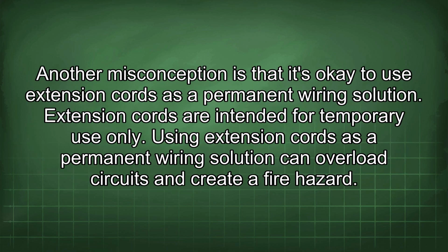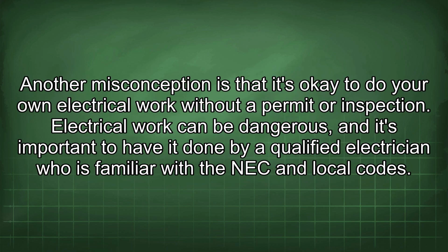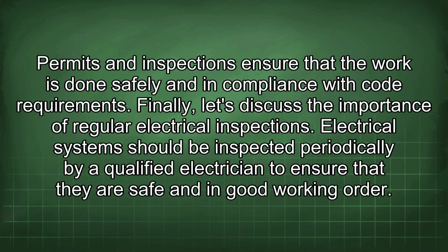Another misconception is that it's okay to use extension cords as a permanent wiring solution. Extension cords are intended for temporary use only. Using extension cords as a permanent wiring solution can overload circuits and create a fire hazard. Another misconception is that it's okay to do your own electrical work without a permit or inspection. Electrical work can be dangerous, and it's important to have it done by a qualified electrician who is familiar with the NEC and local codes. Permits and inspections ensure that the work is done safely and in compliance with code requirements.